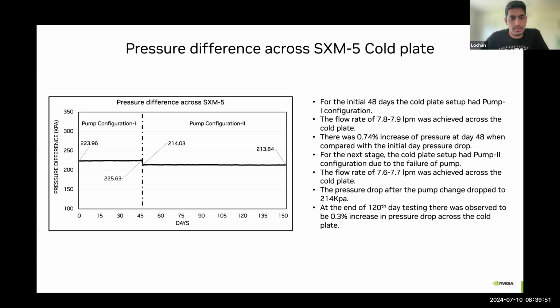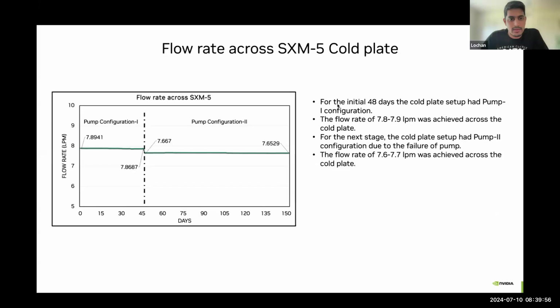Looking into the flow rates, Pratik, next slide, please. The flow rate initially observed in the pump one configuration was around 7.89 LPM. At the end of 48 days of testing, it came to 7.86. After the pumps were swapped with a new one, we were able to achieve a maximum flow rate of 7.66 LPM. At the end of testing, it dropped to 7.65, a change of about 0.1 LPM in flow rate.